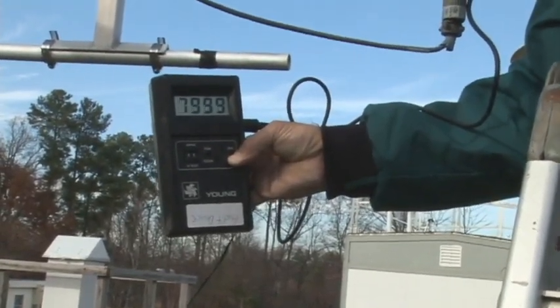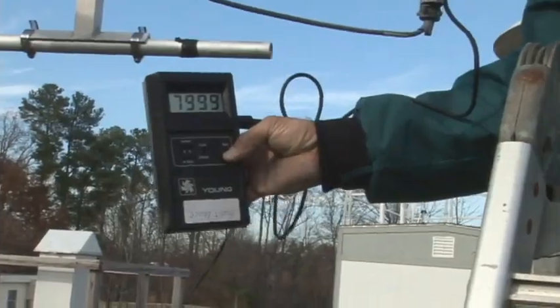Once all of the points are generated and recorded, compare the recorded results against the slope-intercept generated values. If these are within specifications for your program, then the sensor or DAS does not need to be adjusted. If adjustments are made, it is recommended that you rerun the calibration points with the calibration device to reaffirm that this is true. This concludes the motorized calibration of the sensor. The torque test should now be performed.